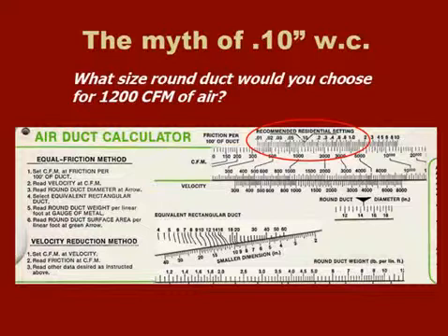First of all, this duct calculator that you picked up is only good for plain round metal. Any duct calculator you pick up that's not stated otherwise is for plain round metal. Let me go over each of those one at a time. Plain, not lined duct, not fiberglass duct board, not rigid round. Plain round. Round, not rectangular, not oval.